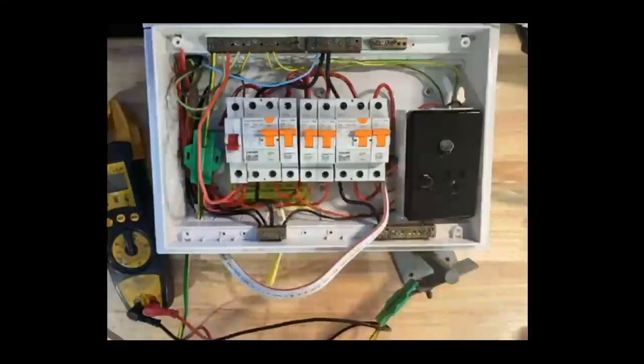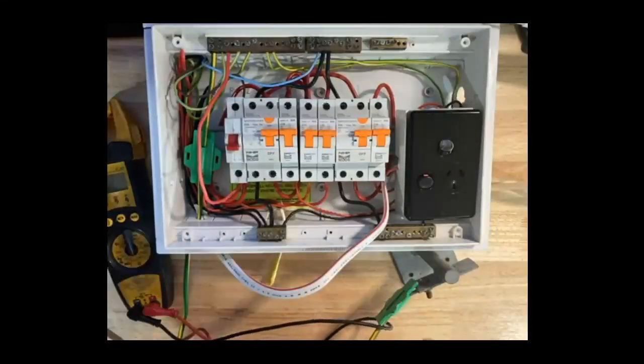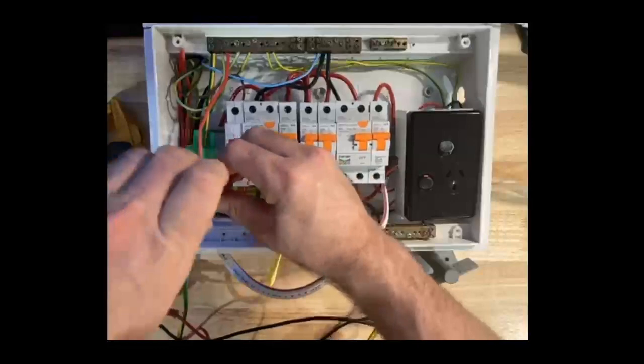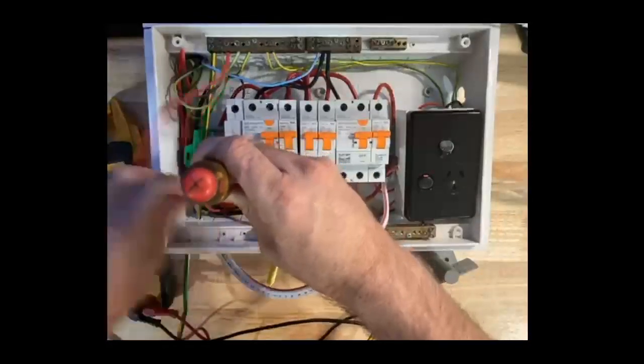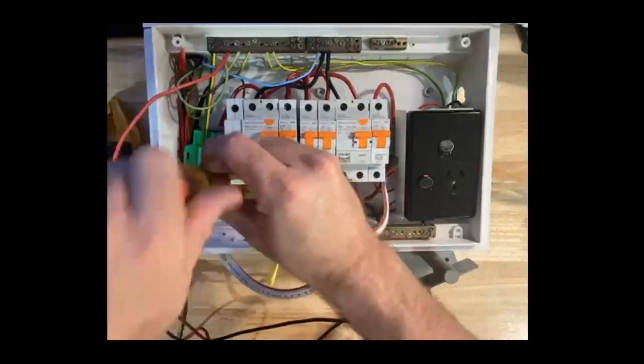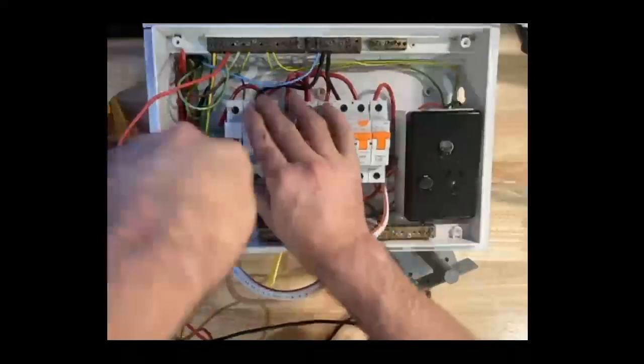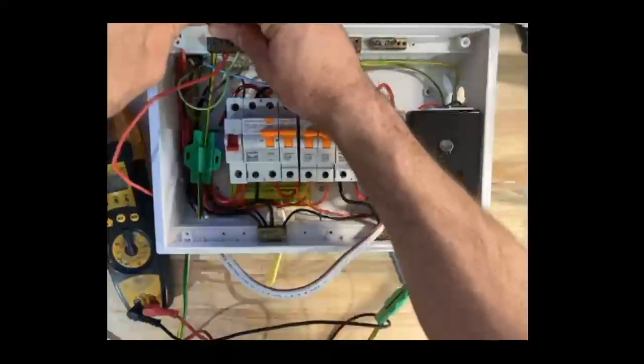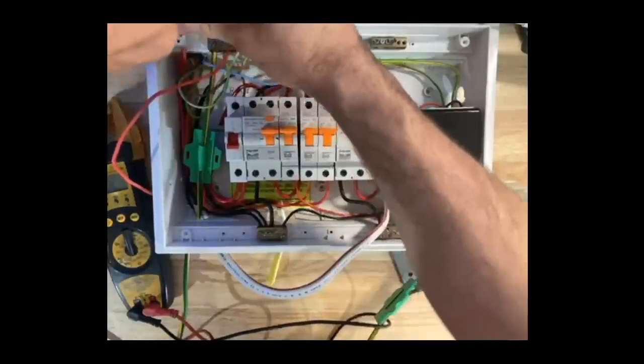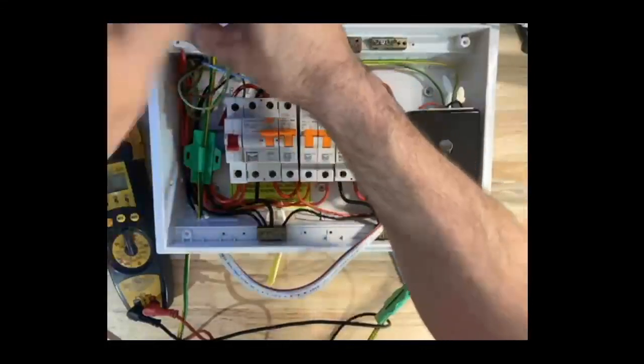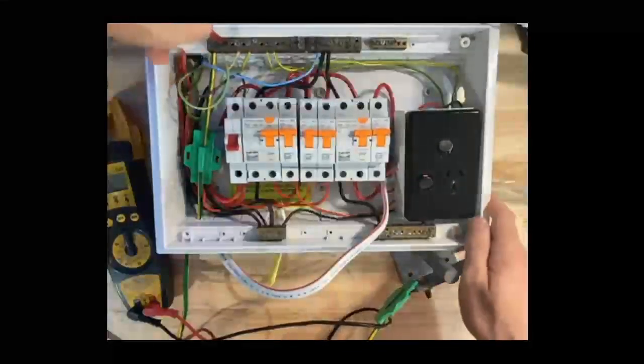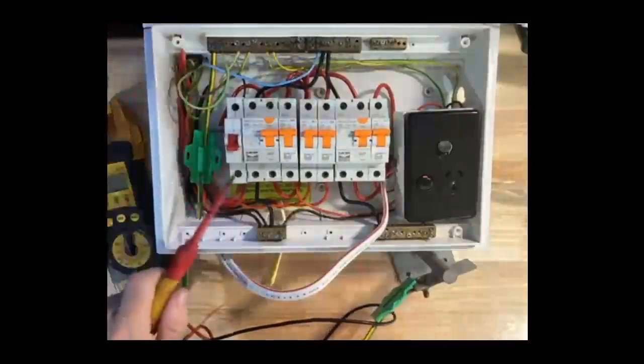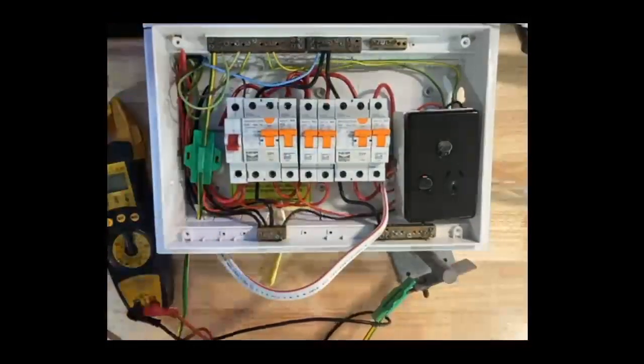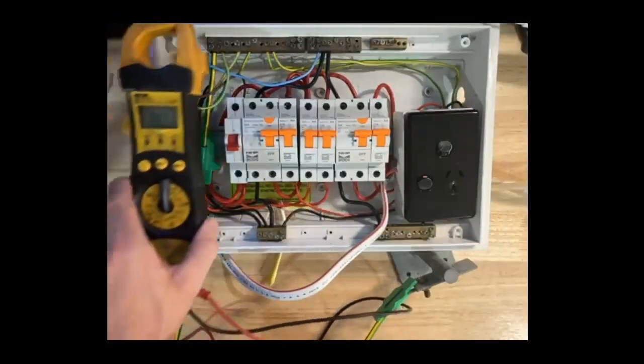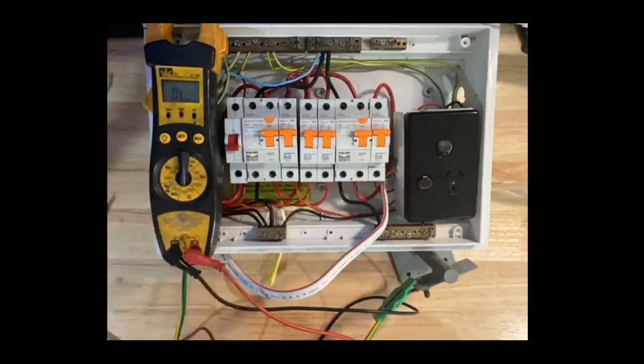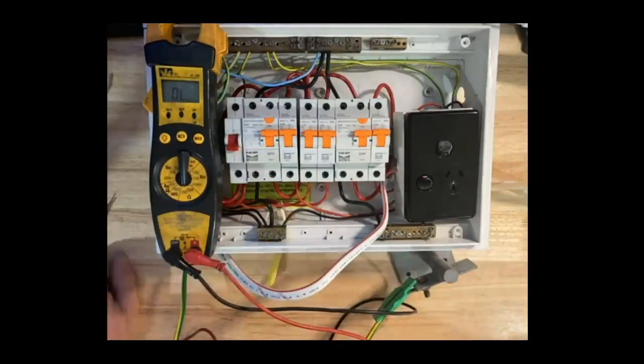So I connect that up, do my earth continuity testing all the way around the house, and then I'm going to disconnect it. So I'm going to do that. Now I'm not going to liven the switchboard, so it doesn't matter, but just so nobody is left with any confusion, I'm removing this extra piece of wire we put in there immediately after finishing testing, because if I accidentally left that in and then livened my installation, I would be in big trouble. Bad things are going to happen.